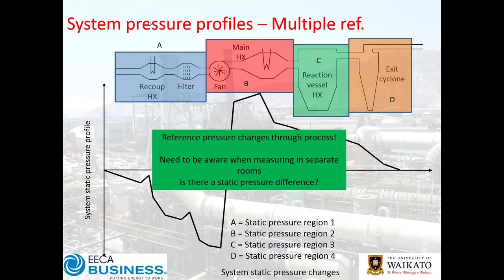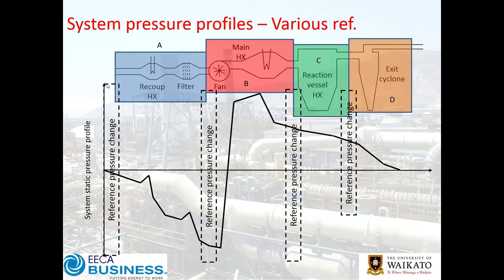You can have multiple zones — A, B, C, D — where cyclones might be a hazardous sealed-off area at a different pressure to the reaction building versus air heating and treatment zones. Each zone has a different static pressure. Depending on industry, internally they're generally kept under positive pressure — though not always. When going from zone to zone, you've got a shift in your reference pressure frame.